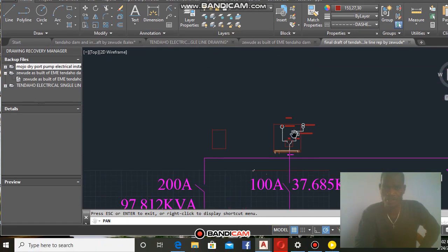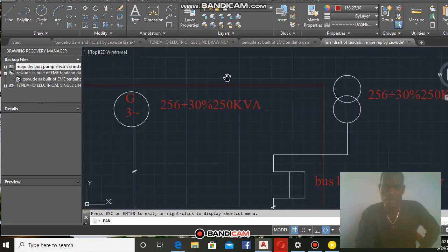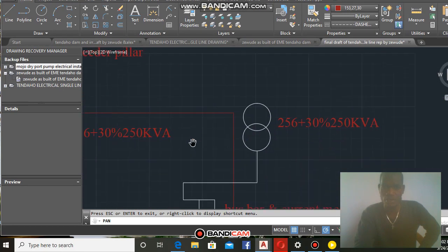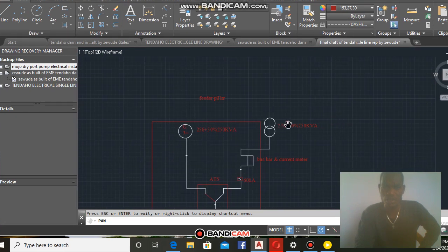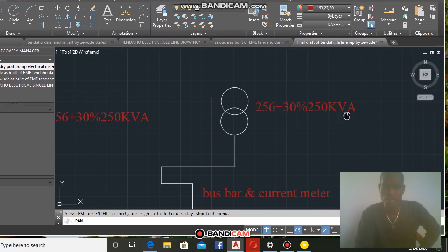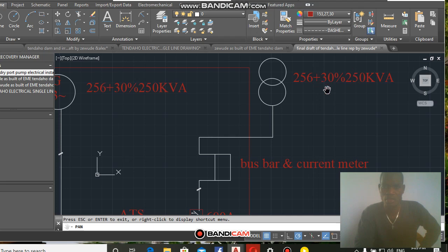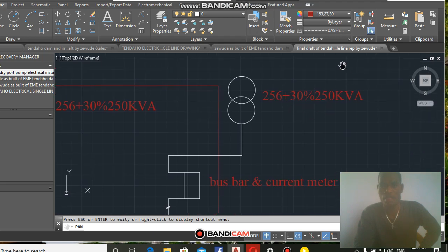Here is my power station — a powerhouse or generator house. In the generator house, there are many things. There is the step-up transformer; its capacity was unknown before I started my assessment, but this is my final calculated result. I presented it in such a manner that 30% is indicated — in every design, you must consider future analysis, such as voltage drop and line extensions. For that purpose, I added 30% to my total KVA.